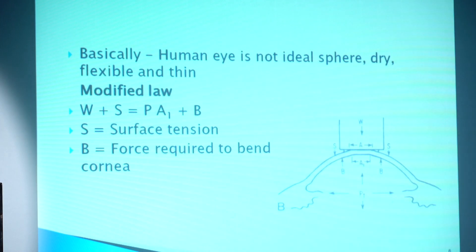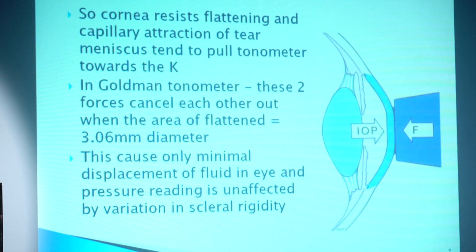To account for this, the modified rule is: W plus S equals P times A1 plus B. The corneal rigidity, flattening, and capillary attraction of the tear meniscus tend to push a tonometer toward the cornea. In the Goldmann tonometer, these two forces cancel each other out when the area of flattening equals 3.06 mm in diameter, and this causes minimal displacement of fluid in the eye.